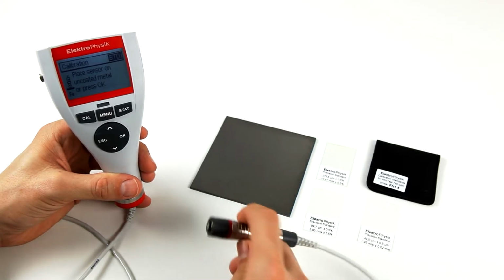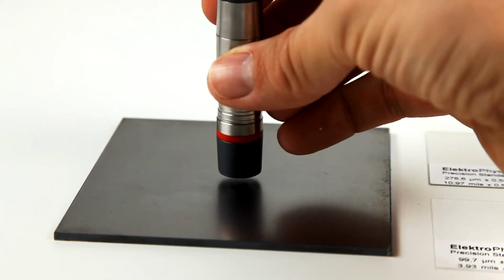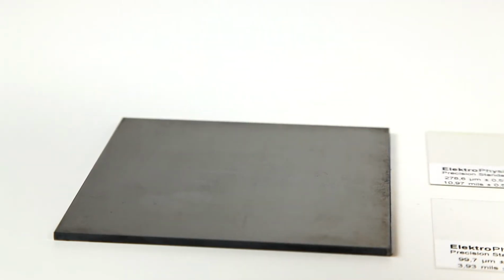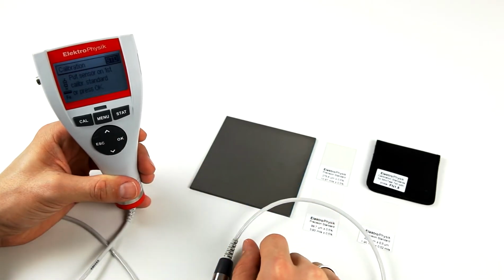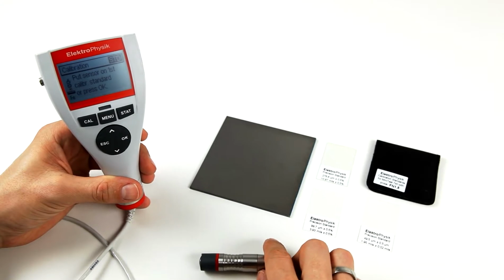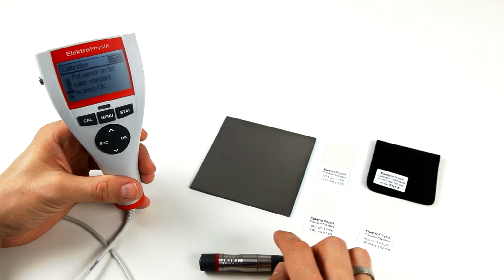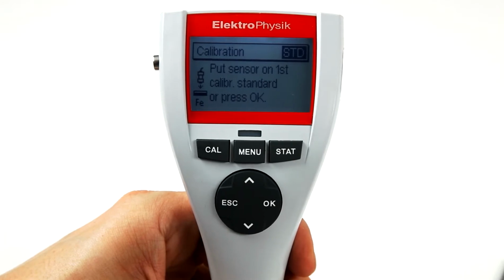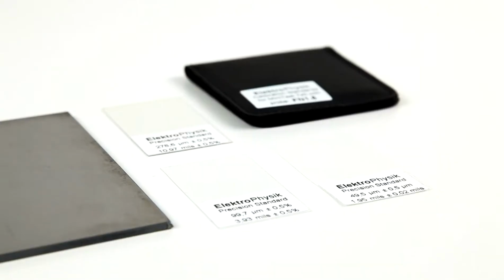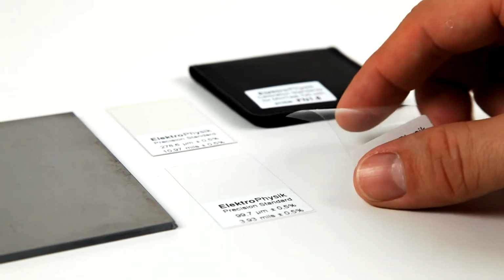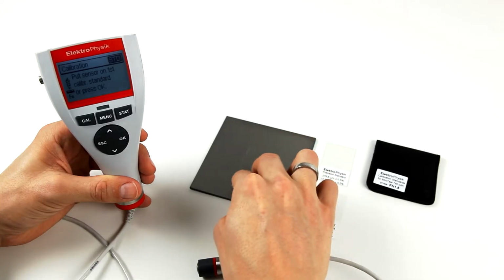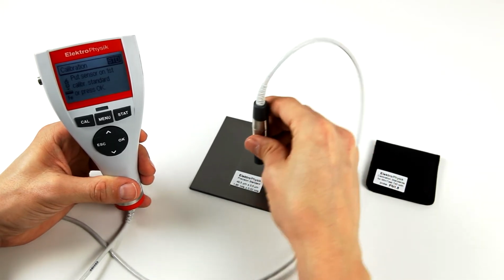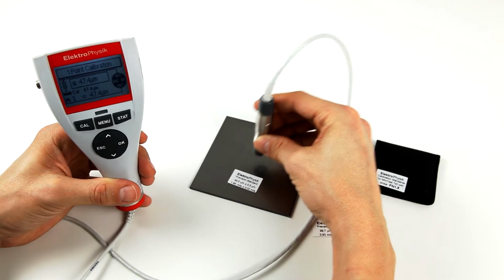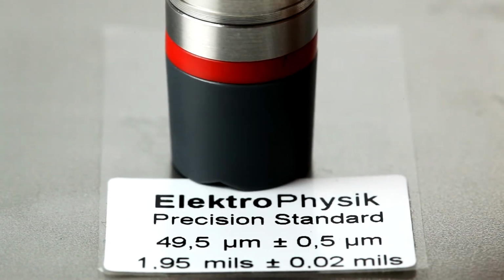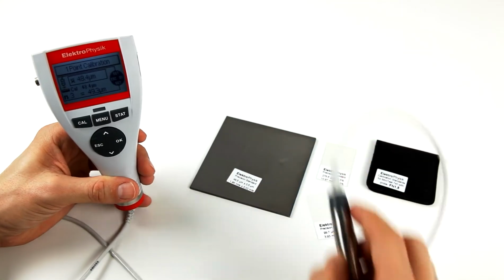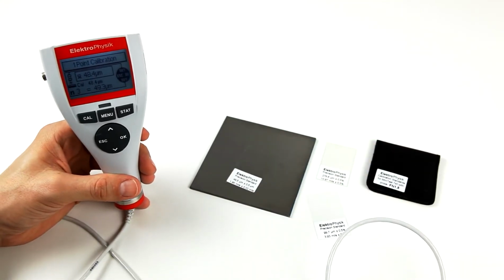Firstly, take a zero reading with the gauge and confirm the zero reading by pressing OK. Any existing calibration will be replaced by the new value. The gauge now displays: place the sensor on the first calibration standard or press OK. Take a calibration foil from the set, place it on the zero standard and take 2 or 3 readings. In order to obtain the highest precision of readings, it is advisable to perform the calibration with a calibration foil whose thickness is close to the thickness of the coating to be measured.